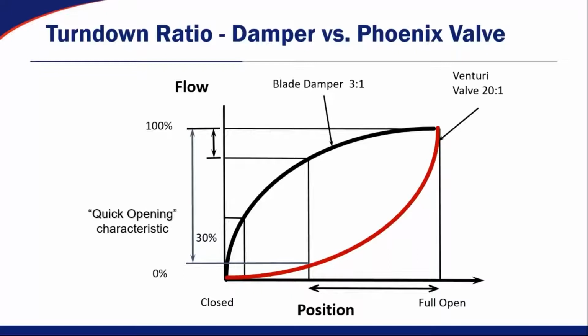Now, if we look at the turndown ratio between a traditional VAV damper and a Phoenix controls valve, they kind of look inverse of each other. So if you look at how a VAV box works, which is that black line, the way that they typically function is when they're in shutoff mode, as soon as they crack that blade open in the ductwork, you're going to get about 30% of your airflow. So it has what we consider a quick opening characteristic. And then really what you have is controllability between about 30% airflow and about 70% airflow, maybe a little bit higher. And that typically gives you about a 3-to-1 or a 4-to-1 turndown ratio on a VAV box.